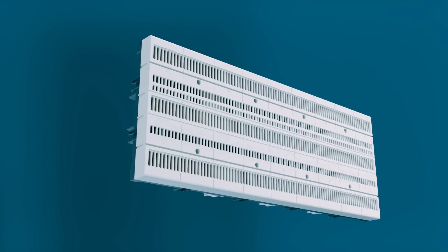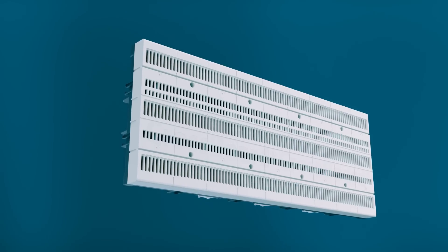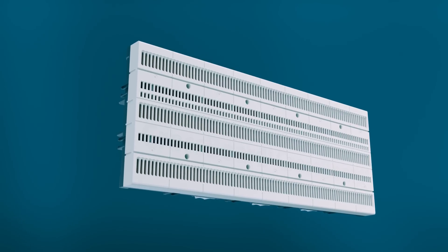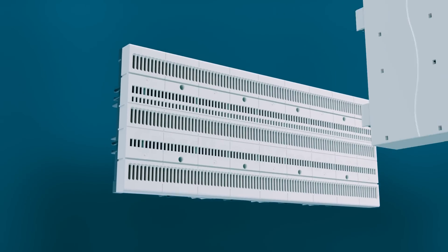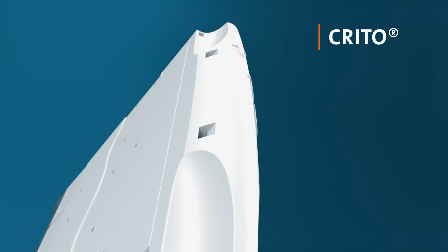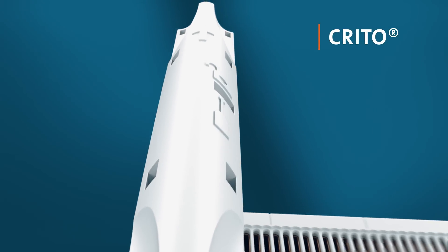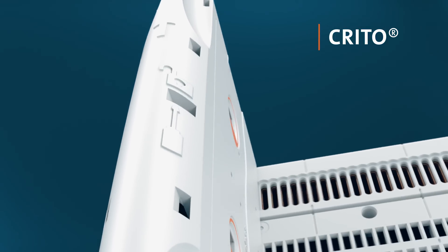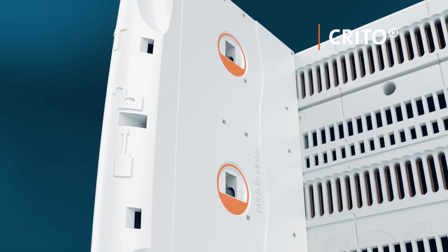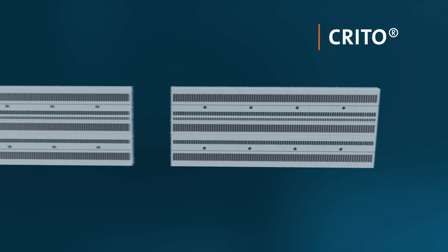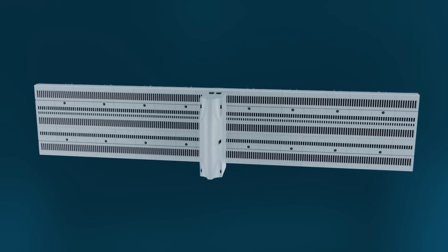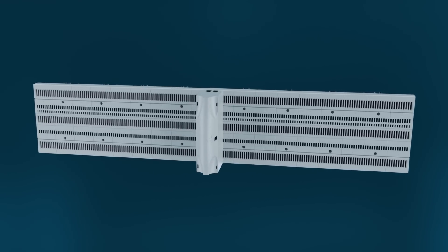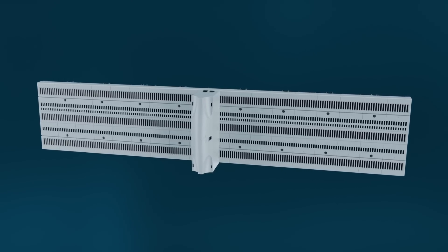Different components make the Crossboard a suitable power distribution system. The Crossboard can be fed with the CRITO connection modules with cables from 16 to 50 square millimeters. If required, the 45 mm wide CRITO can be used to center feed two Crossboards.